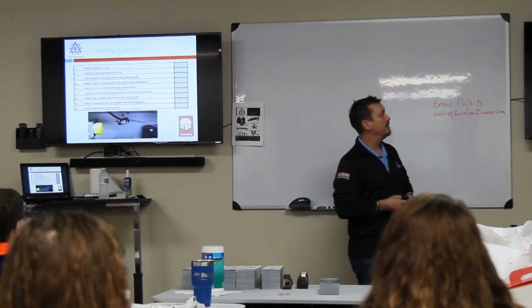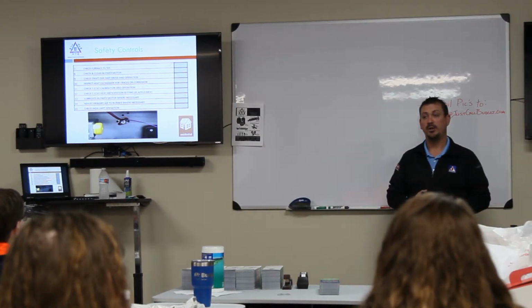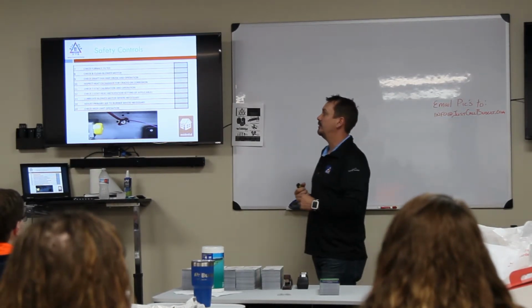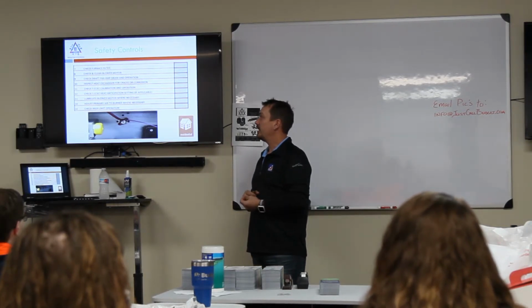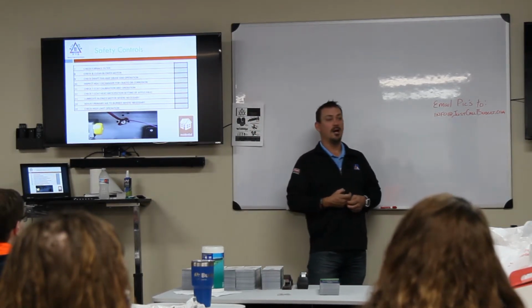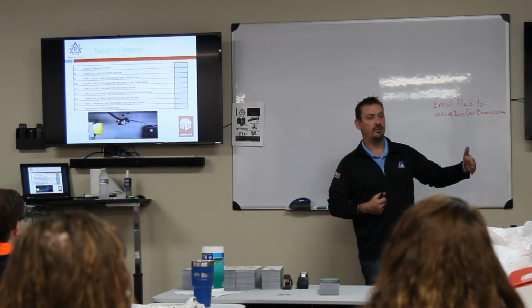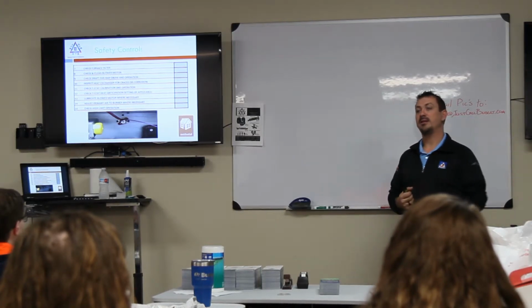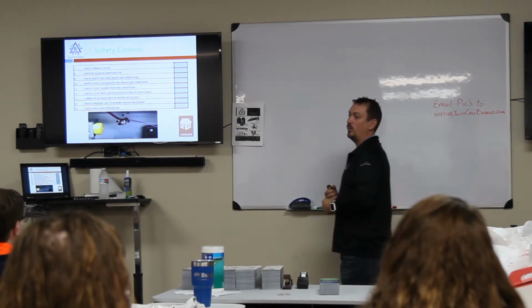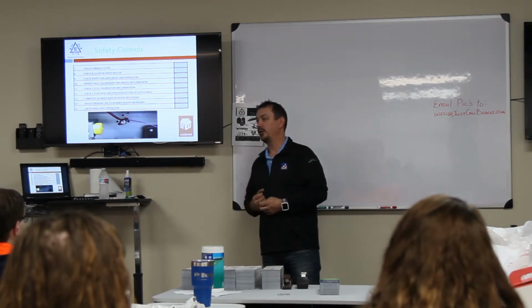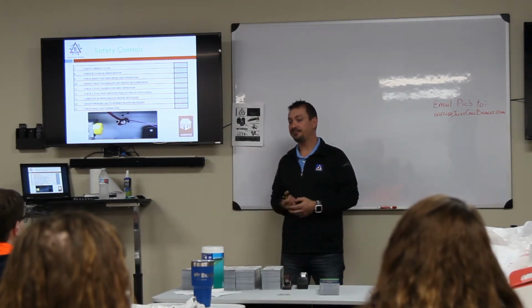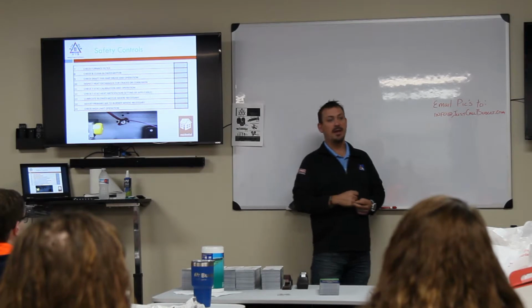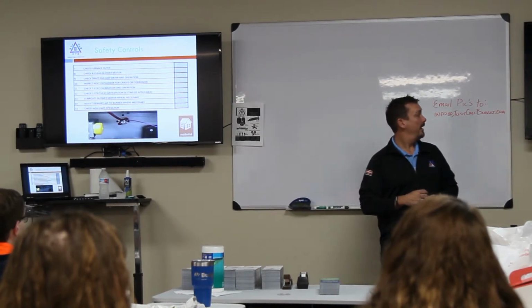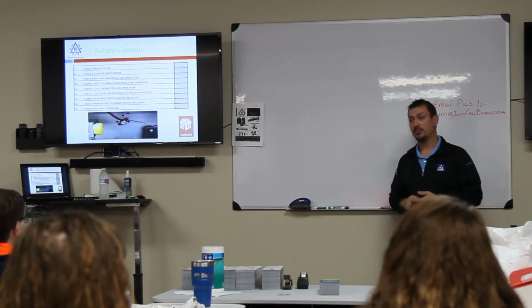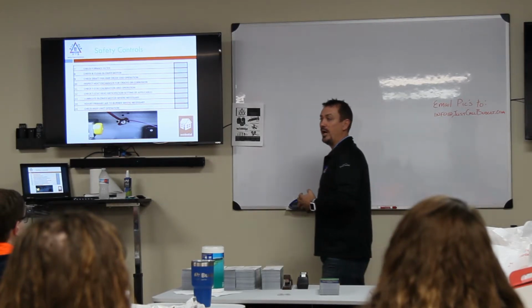Next, we're going to go ahead and check the filter, like we just talked about. We're going to check the filter, make sure it's nice, clean, and clear. Check and clean the blower motor and wheel. If the filter has been out for a while, or you see a lot of dust and debris on the end of the blower motor, go ahead and clean it off so we can get good airflow across the motor itself. And then you're going to go ahead and check the inducer motor, making sure it's operating properly.